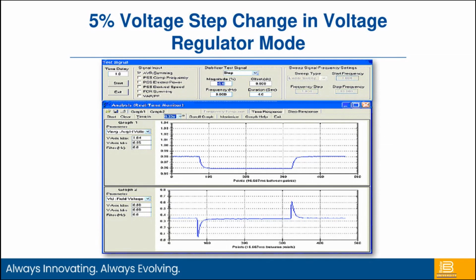So this is a very stable generator, very stable response. And then I'm going to step back up my 5%. We're going to see that output spike in the generator voltage, and then it collapses down and creates that stable response. So what this is really showing is our exciter field reacts much quicker than the output of the generator. That's because of time constants. So that's what we're tuning to, the time constants of the exciter field and the generator field, which is why we need to change those based upon each particular machine. Time constants vary between different sizes of machine, different makes of machine, and so on and so forth. So PIDs allow us to be very flexible and match our output based upon the reaction of the machine.